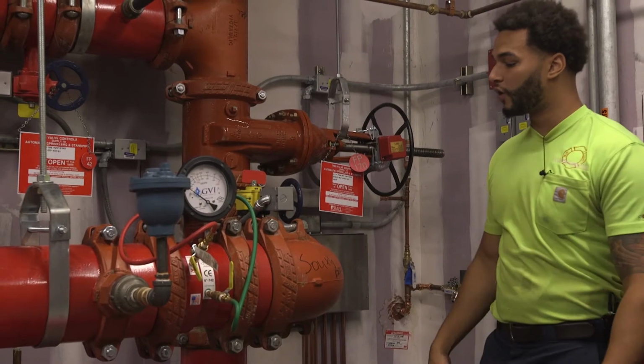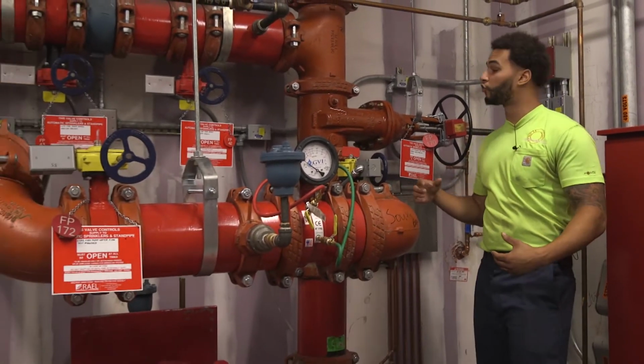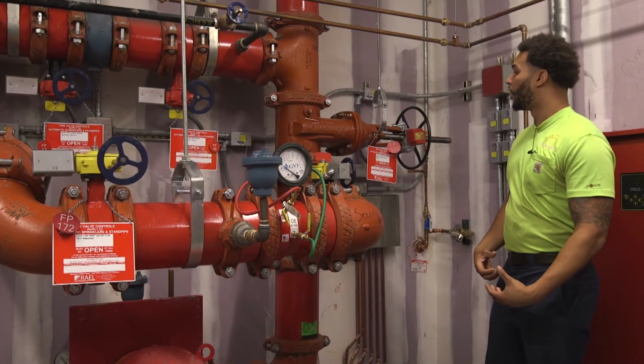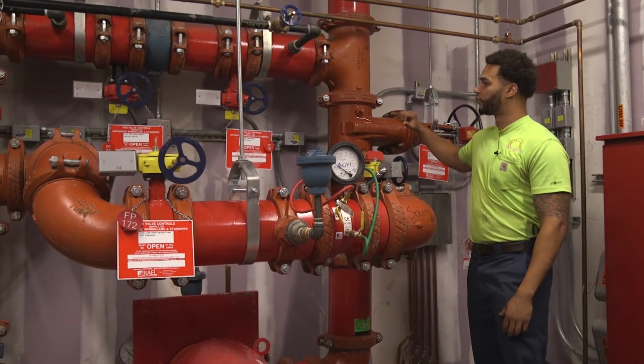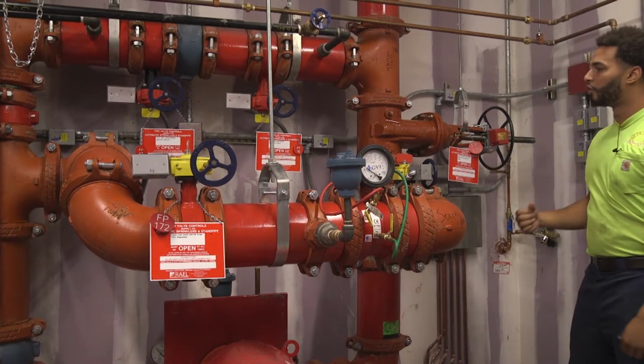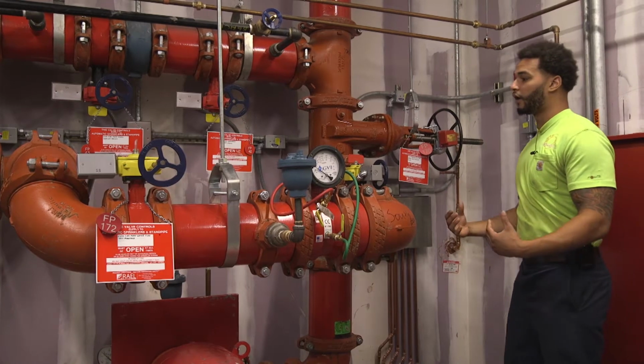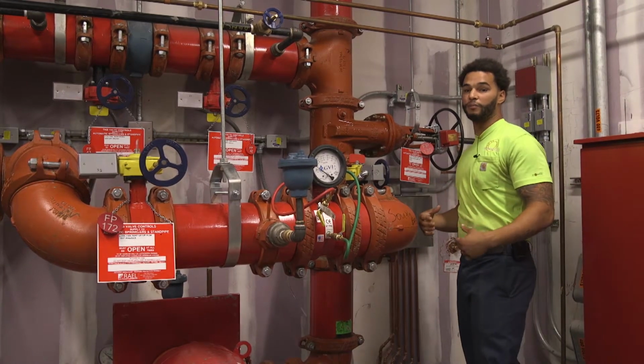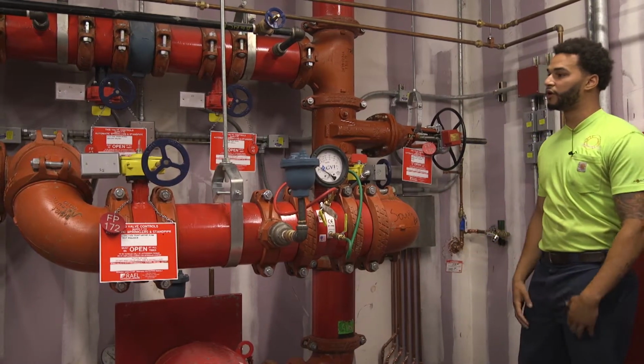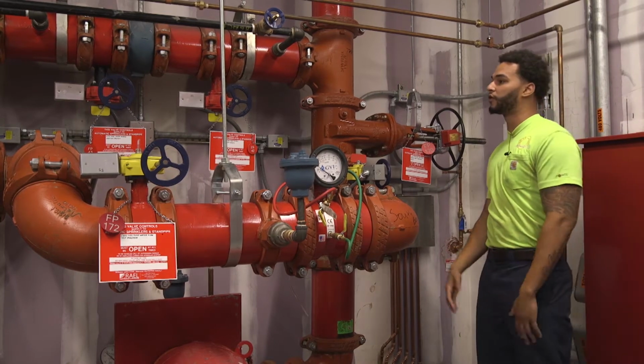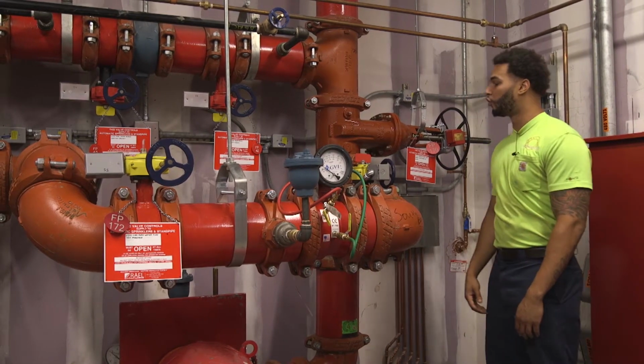As for mechanical and chemical hazards, when this fire pump operates, we are creating turbulence with water and putting mechanical stress on the piping itself. So when we operate this fire pump, we don't want more than 2 people in the fire pump room while it is operating, for safety purposes and so everyone can evacuate if anything goes wrong.